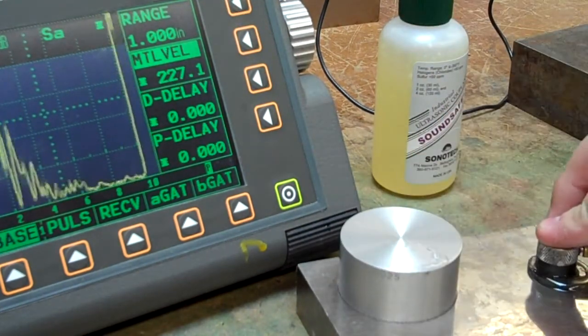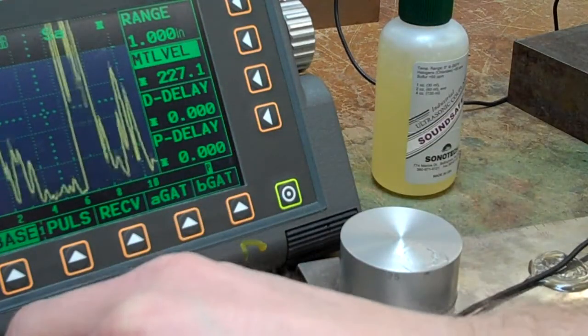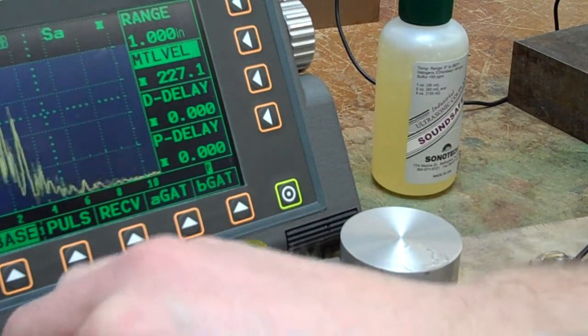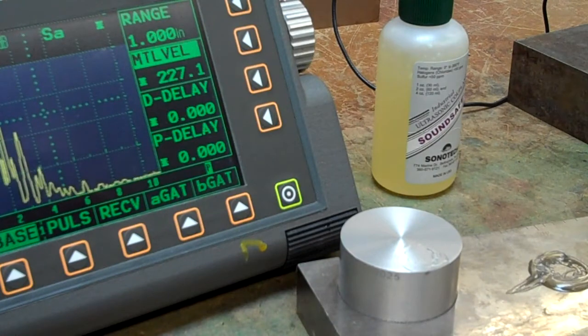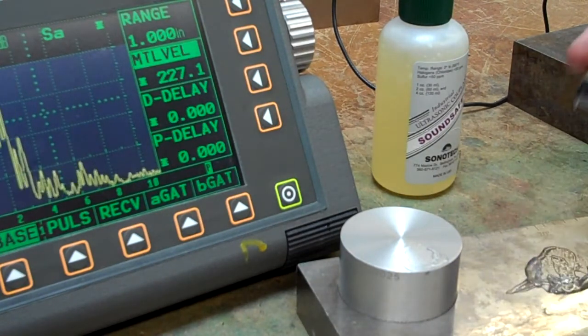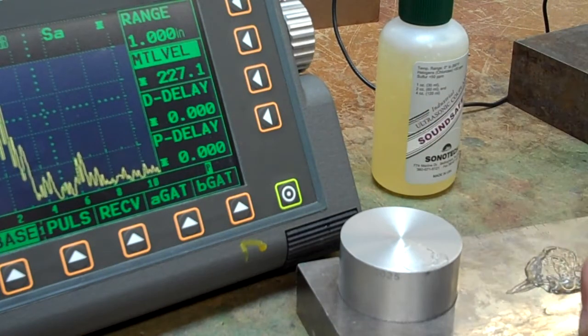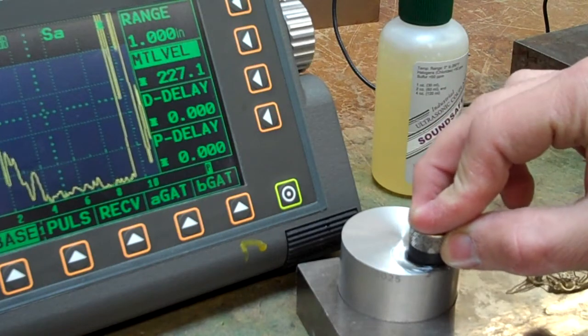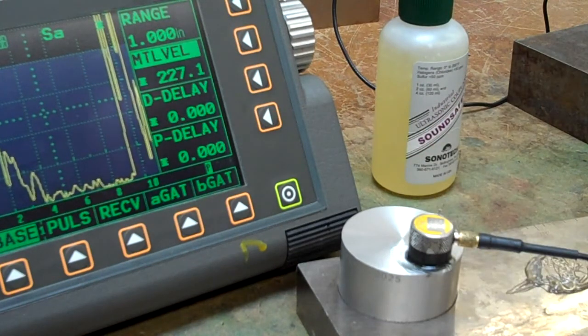Here's our piece of steel, 1-inch. Over here, we know that's 0.625. Over here, we know it's way past an inch. Now we go to our aluminum again, and it comes up at about 94% one last time. So we can quickly figure: V1 times T1, velocity 1 times thickness 1, divided by thickness 2, equals velocity 2.